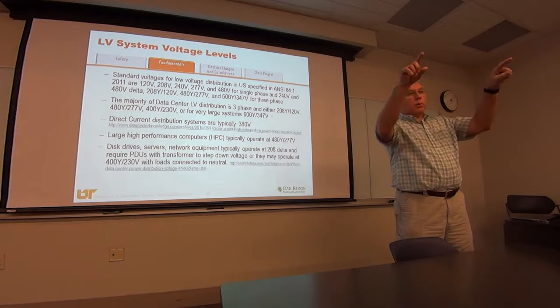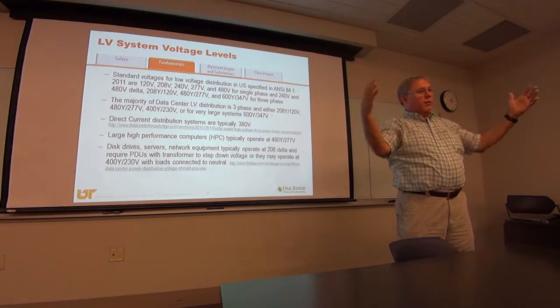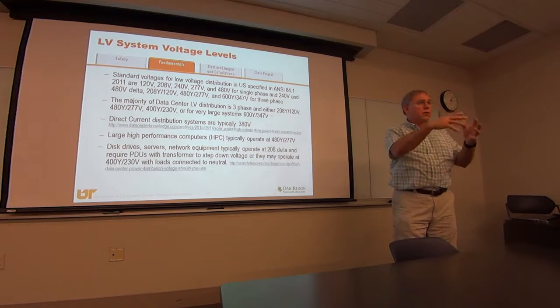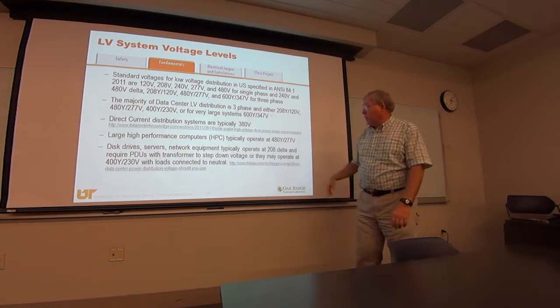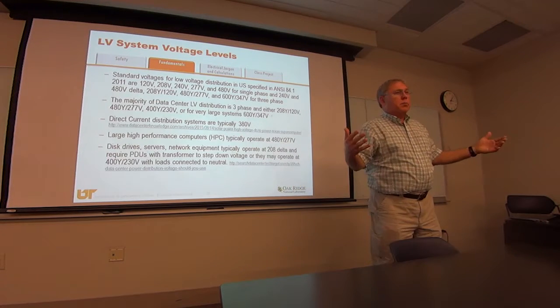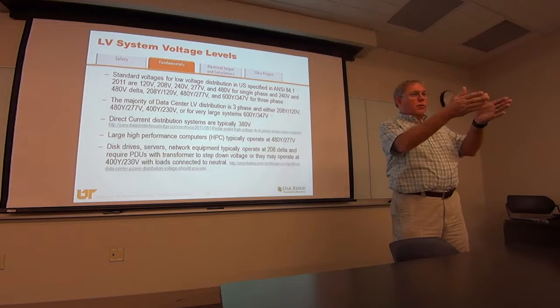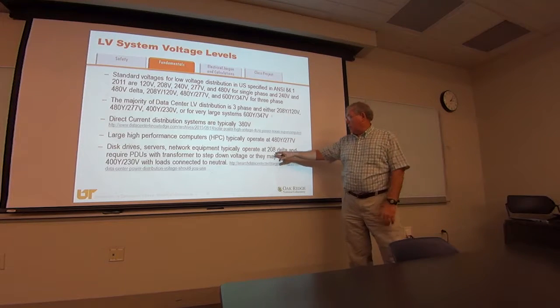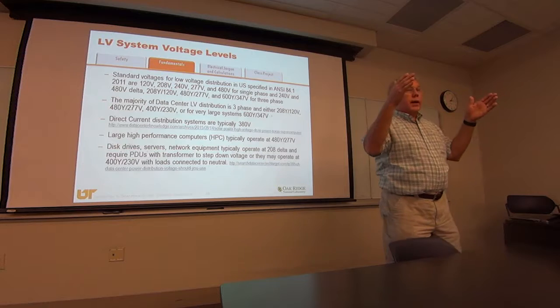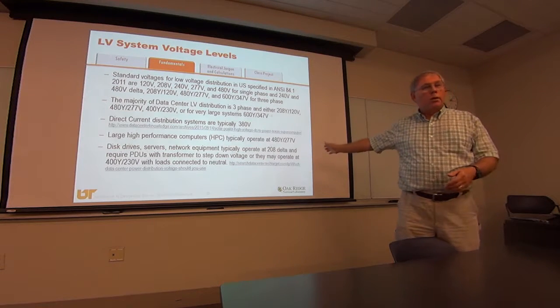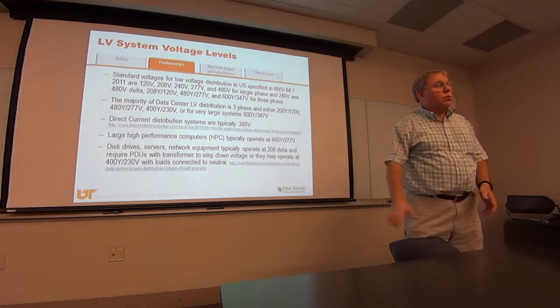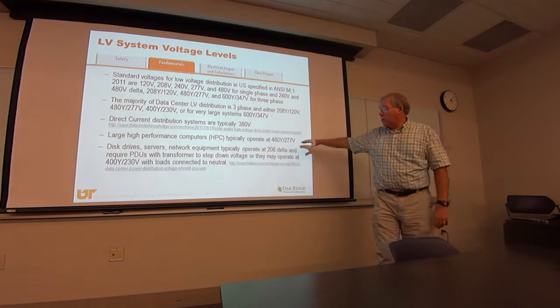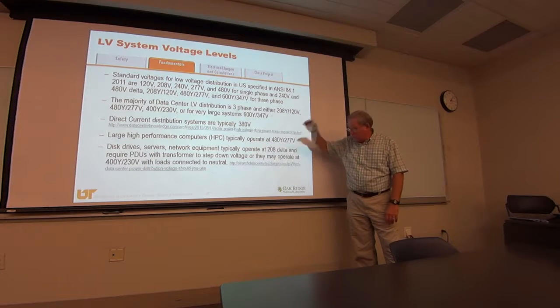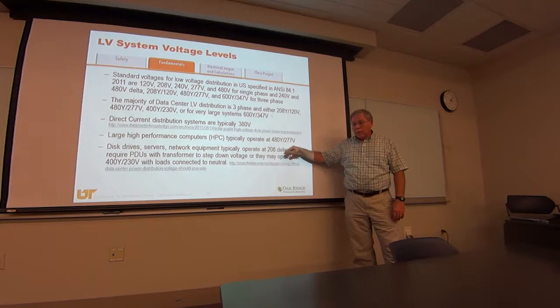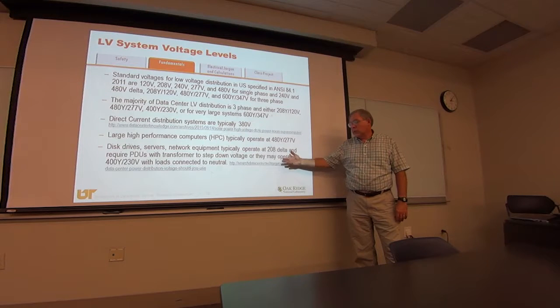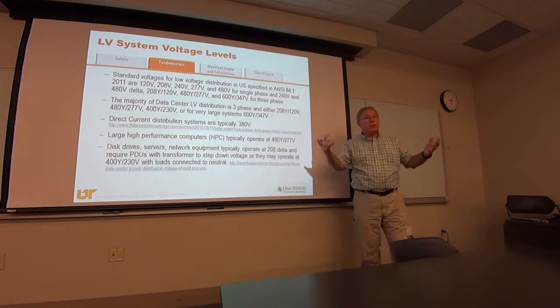If we put in a 480 volt power supply, they get much bigger because you have to have more spacing. And the breakers and the switches also have to be rated higher. Plus we're running 80 kW into a cabinet. Your cabinets are 10 kW. This is a good voltage for a 10 kW cabinet. But an 80 kW cabinet takes 8 of those wires going into a cabinet. So we run a 100 amp circuit at 480 volts. So we use the 480 volt for the bigger systems. And typically for a network, servers, disk drives, 208 volts, sometimes 230.